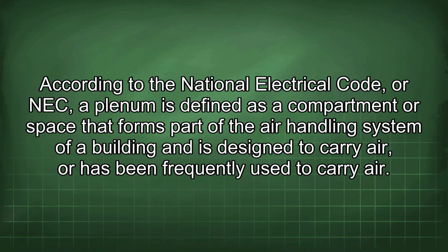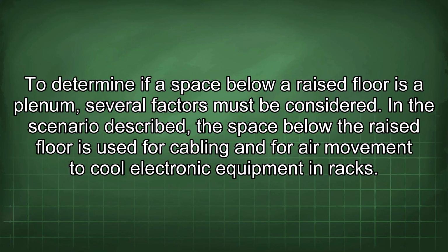According to the National Electrical Code, or NEC, a plenum is defined as a compartment or space that forms part of the air handling system of a building and is designed to carry air or has been frequently used to carry air. To determine if a space below a raised floor is a plenum, several factors must be considered.